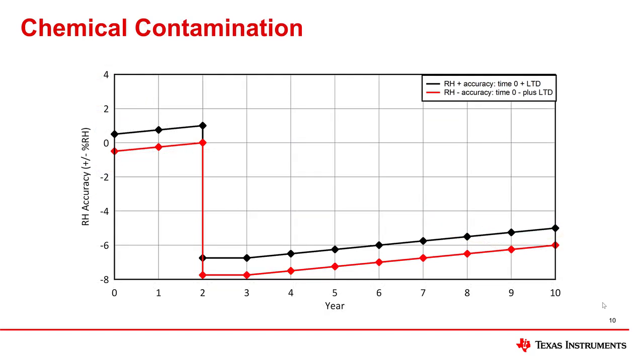This graph illustrates the effect of chemical contamination on a humidity sensor. In year two, the sensor was exposed to a contamination event, which can add much more relative humidity error than a device would generally accumulate over a 10-year lifetime. The effect of contamination is added to the normal effects of long-term drift so that the sensor lifetime accuracy from time zero can be appropriately represented.